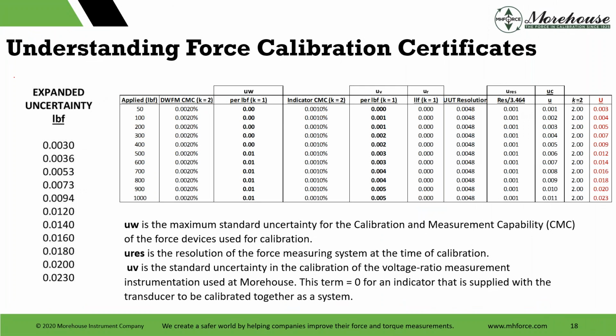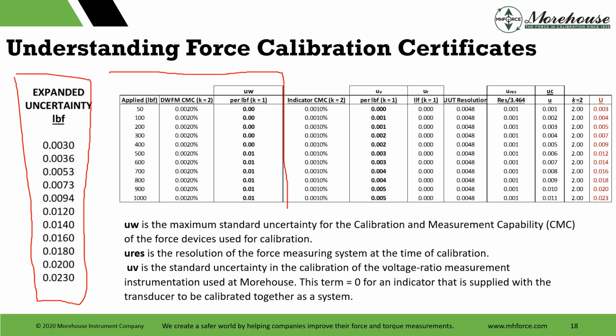We break down this whole expanded uncertainty. How do we report this? What does this mean? How do we get to these numbers? UW is the maximum standard uncertainty for the calibration and measurement capability. That's our standard right here, UW. We're going to multiply all these points by our uncertainty at k equals 2, then reduce it by dividing by 2. And then URes is the resolution of the force measuring instrument. And remember, we said 0.0048. So we're going to use that number.